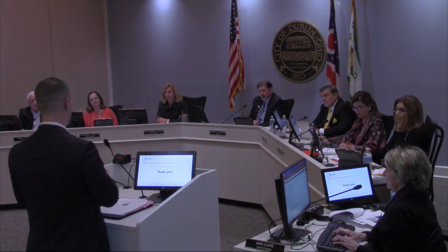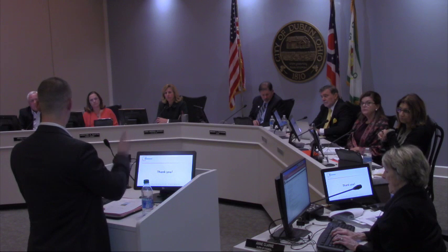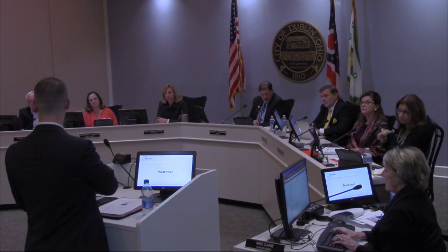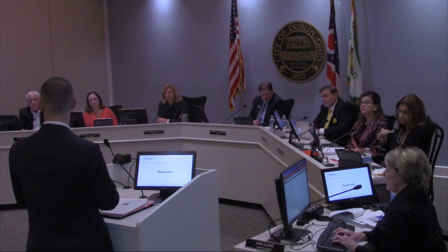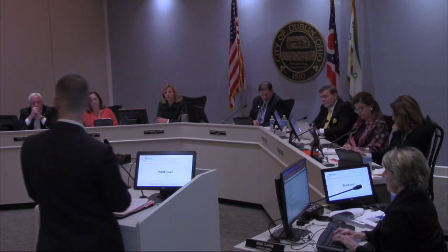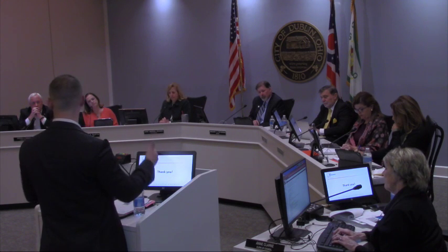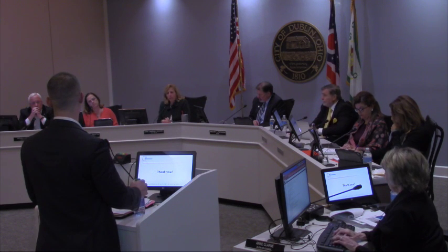Well, not necessarily. So we're only looking at an 80-foot wide right-of-way. What that means is the pole's in the center and then 40 feet of easement on both sides. So when we're by a road, 40 feet of that easement can be overhanging the road. What we're worried about is trees going up into it, buildings being built that impact the clearances that we have to meet. So what is the building clearance on these lines? I don't know the exact clearance. It gets pretty complicated. But that's generally 40 feet on both sides of the center line is what we're going to be looking to have clear. Center line of the power line or center line of the road? Center line of the power line.